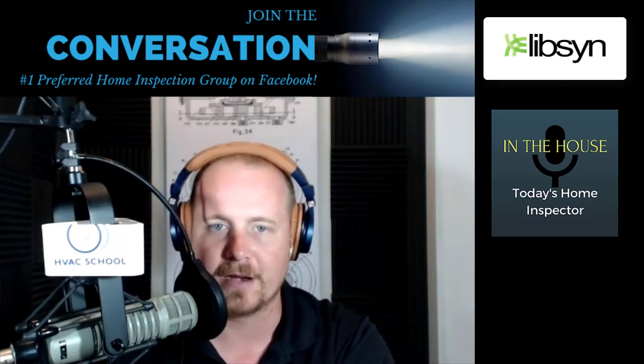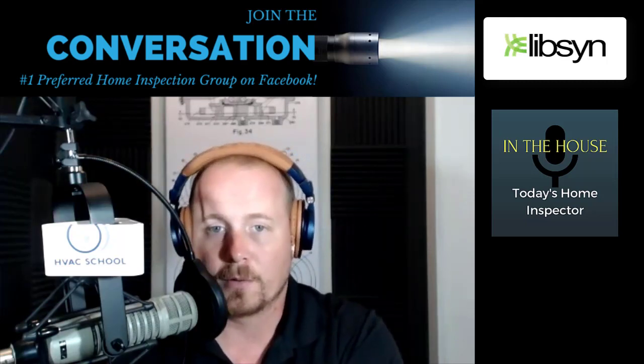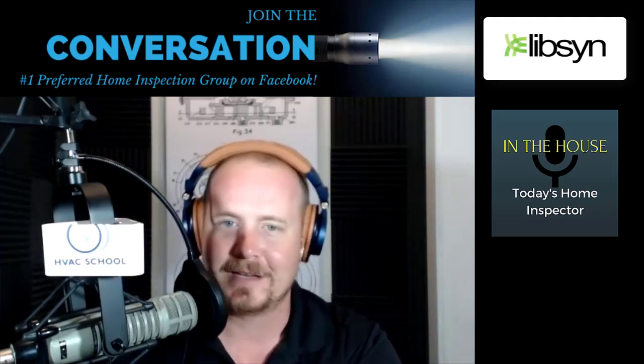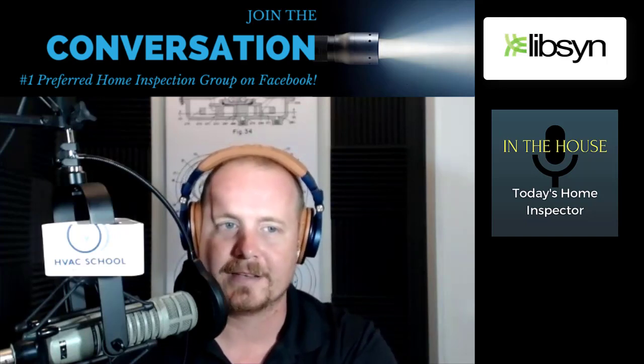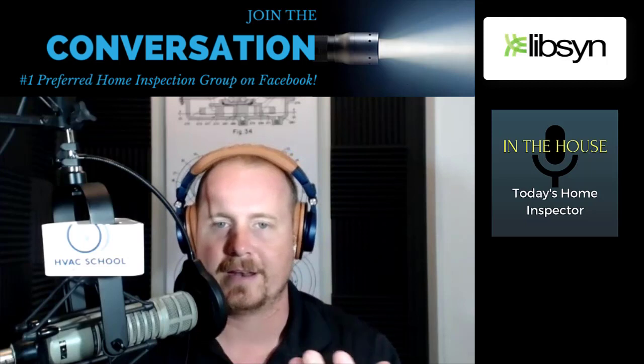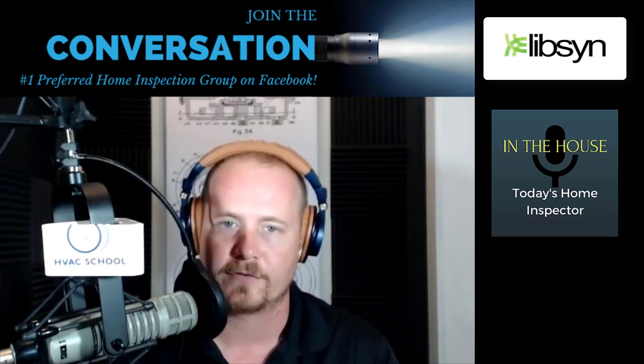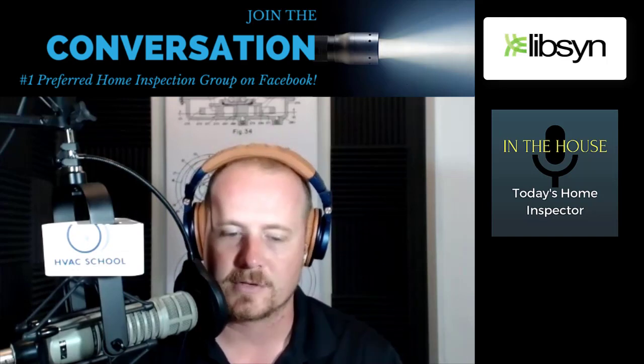You have high humidity. Okay, we're going to use a blower door, but we're not going to use it to see if you're under CFM or ACH5. We're going to look at it to see what your number is and can we improve it, and where we're getting infiltration from, and are your ducts leaking, and those sorts of things.